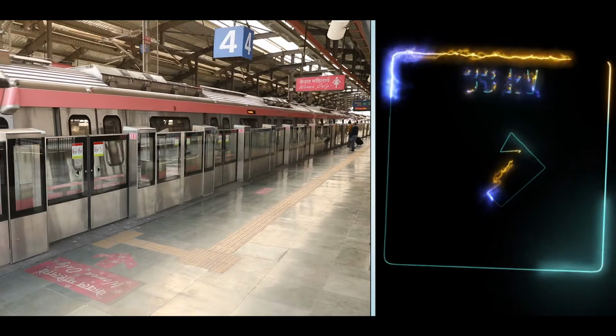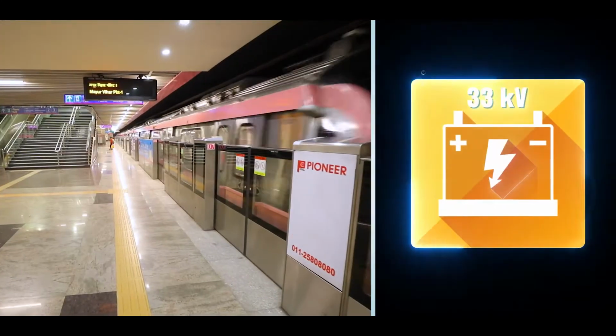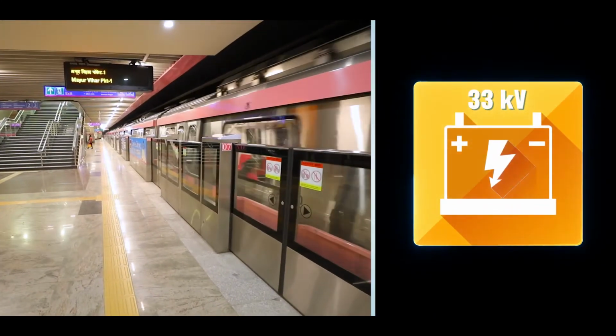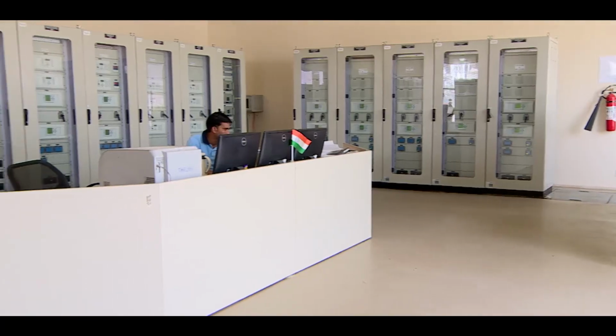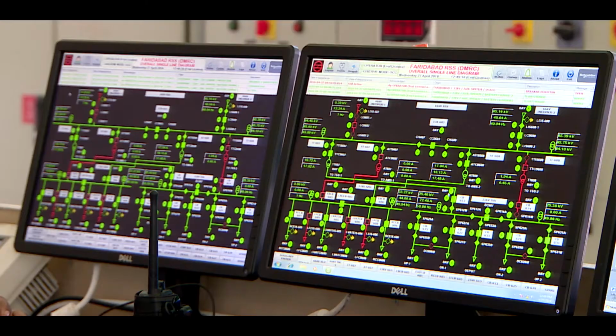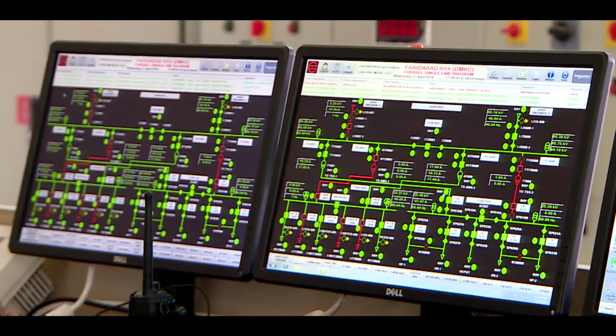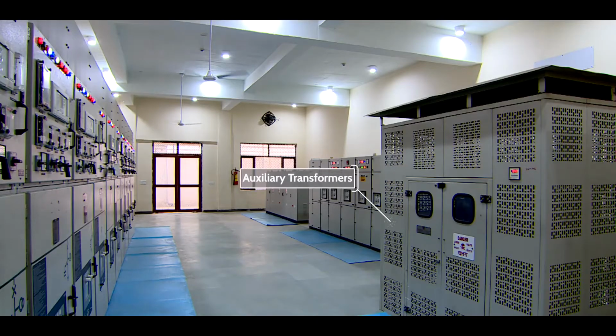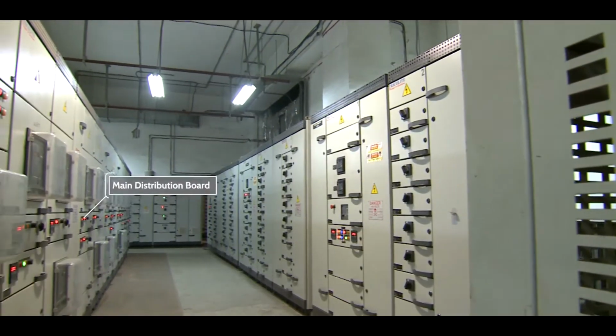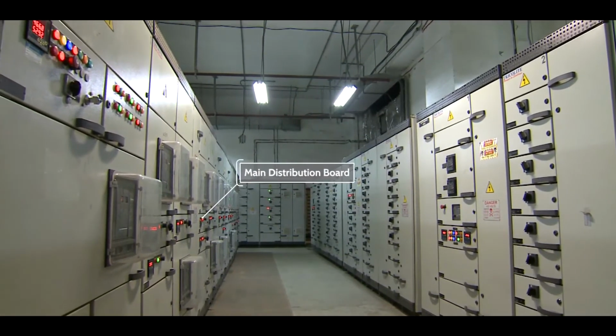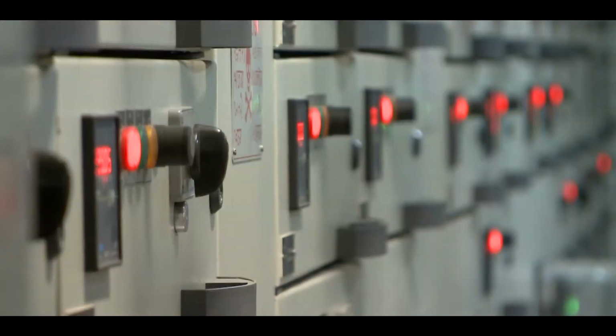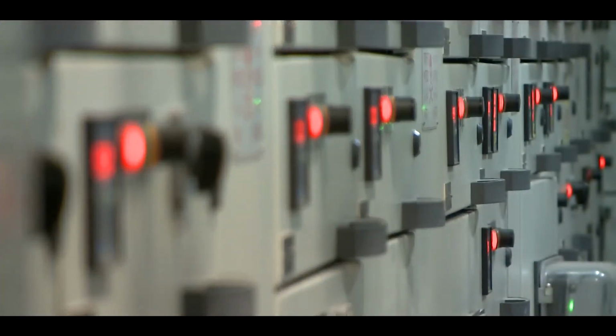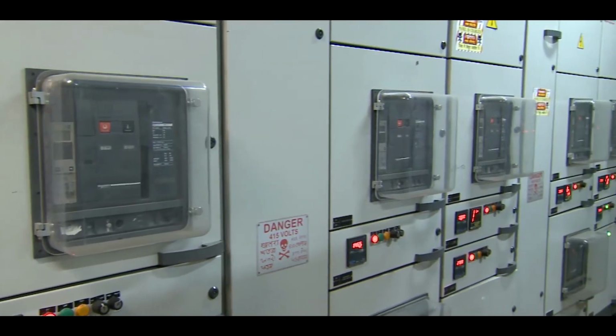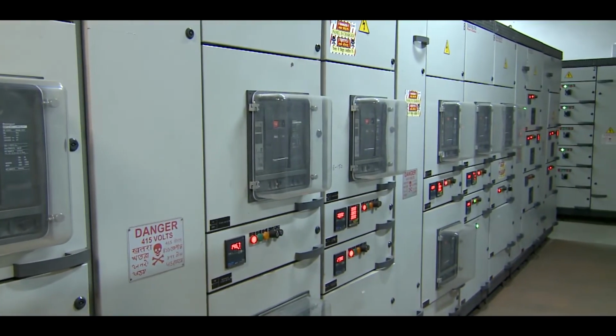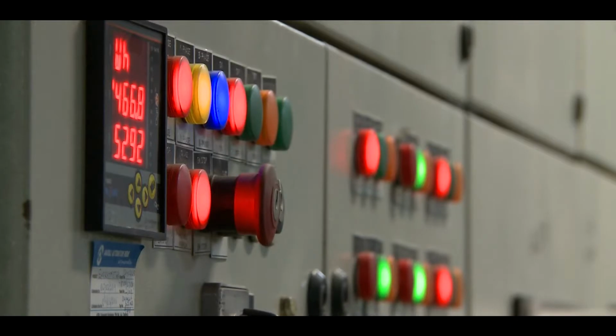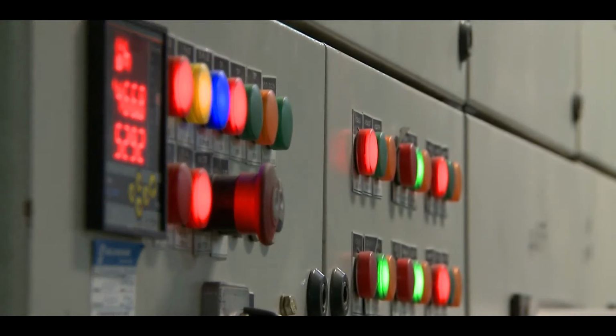Each metro station, whether elevated or underground, is provided with two power supplies at 33 kV. This power supply received at 33 kV is stepped down to 415 V at the station through auxiliary transformers and supplied to the main distribution board, or MDB, which is installed in a room called the auxiliary substation, or ASS. Further, distribution of electricity at 415 V and below is called the low voltage power supply system.